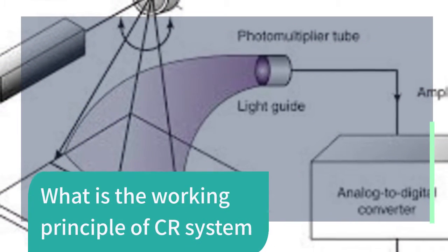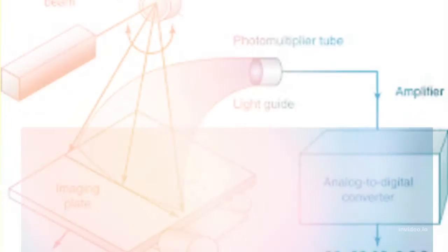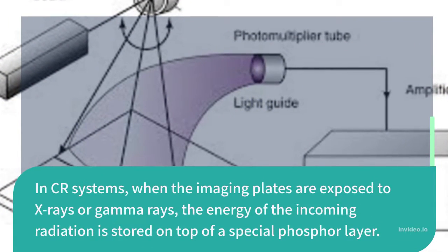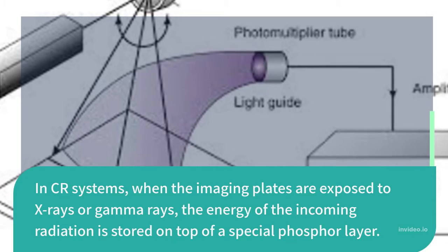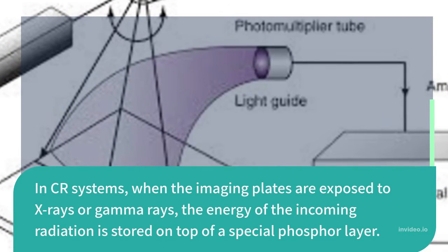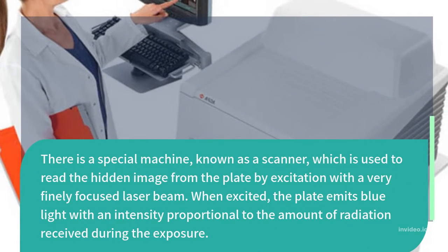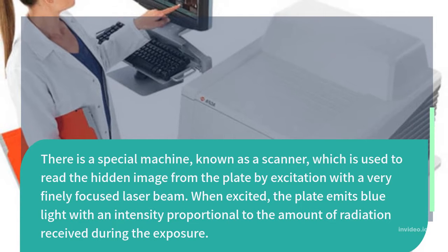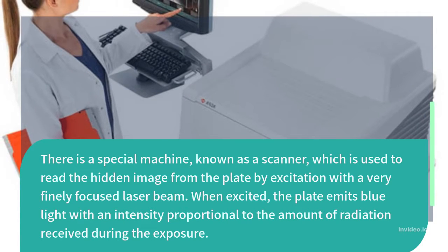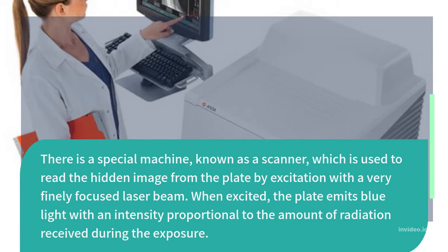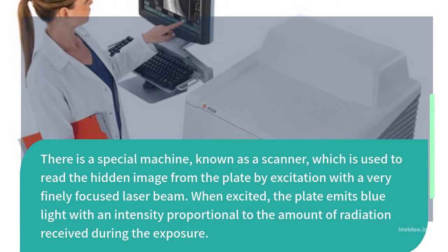What is the working principle of the CR system? In CR systems, when the imaging plates are exposed to X-rays or gamma rays, the energy of the incoming radiation is stored on top of a special phosphor layer. There is a special machine known as a scanner, which is used to read the hidden image from the plate by excitation with a very finely focused laser beam. When excited, the plate emits blue light with an intensity proportional to the amount of radiation received during the exposure.